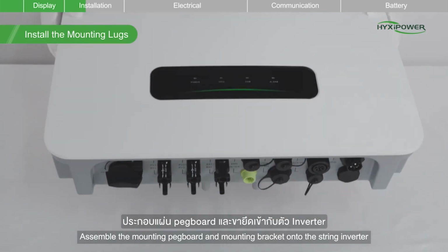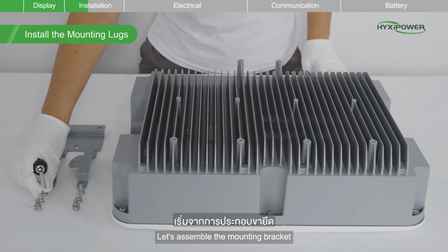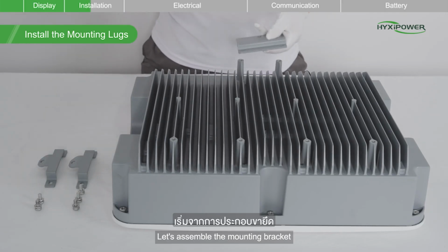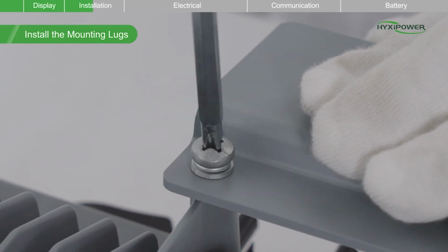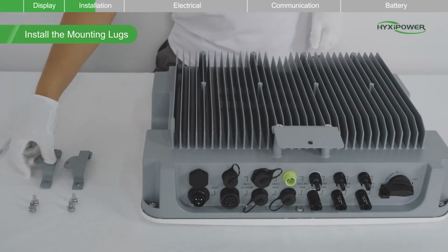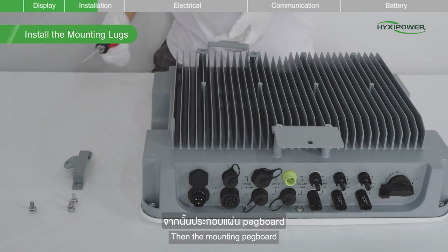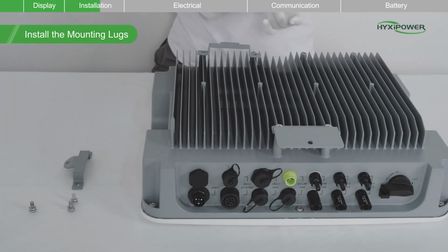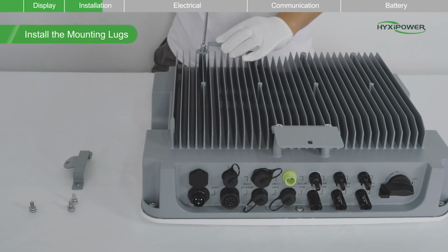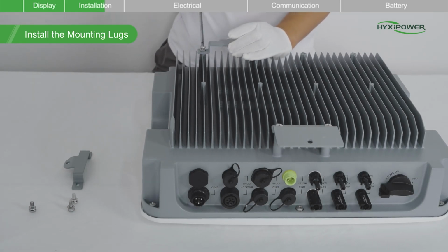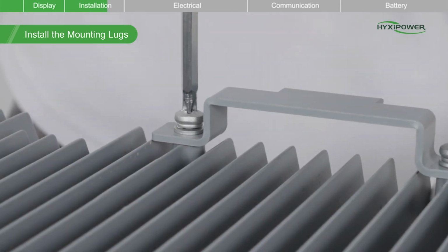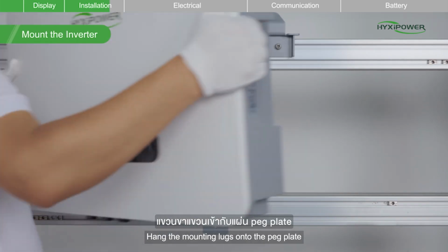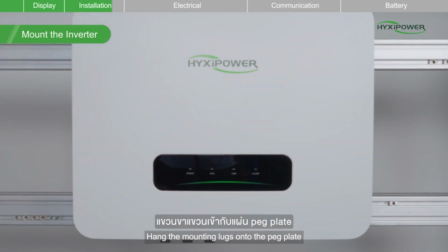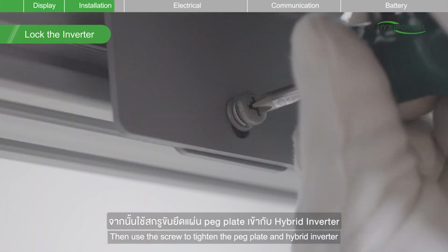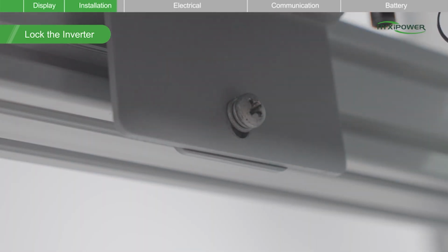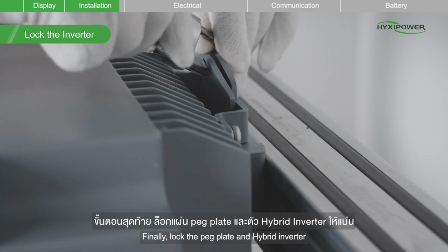Assemble the mounting pegboard and mounting bracket onto the string inverter. Let's assemble the mounting bracket. Then the mounting pegboard. Hang the mounting lugs onto the peg plate. Then use the screw to tighten the peg plate and hybrid inverter. Finally, lock the peg plate and hybrid inverter.